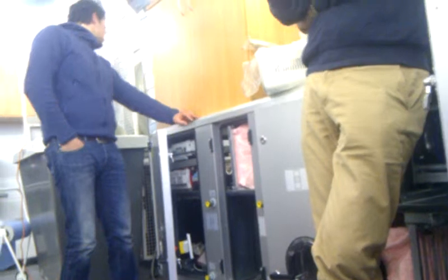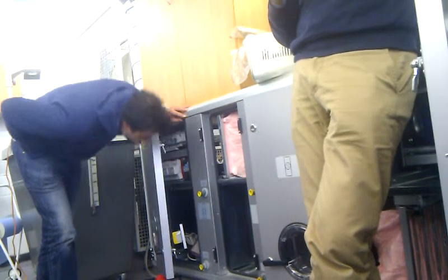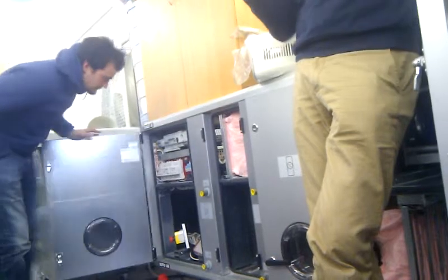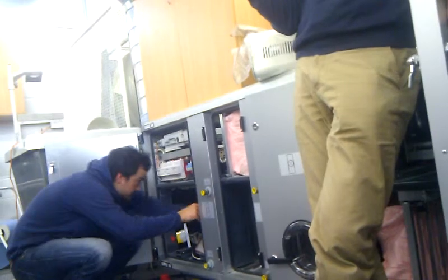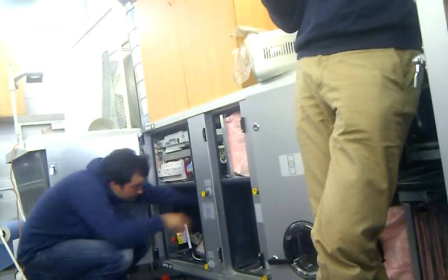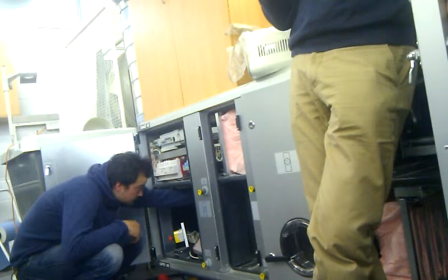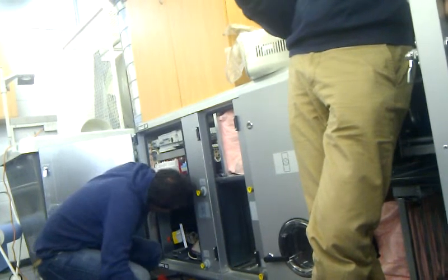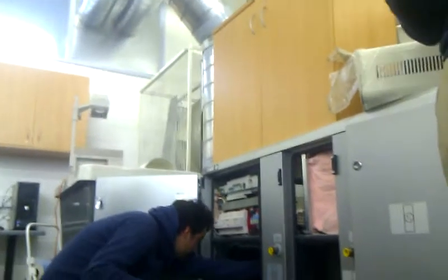G is normally your 24 volt power to power your motor. G0 is normally your negative, and Y is your signal, the signal coming to this. And then you can have a signal coming out to say what position it's actually at, using limit switches and stuff. But I'll get into that if we need.